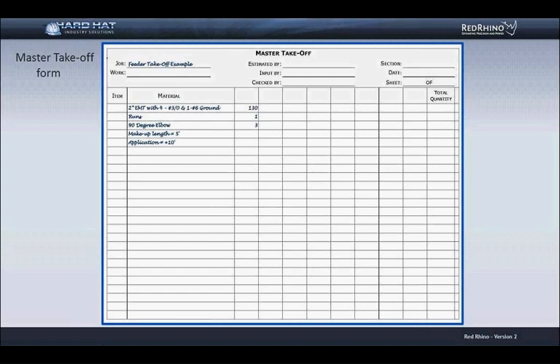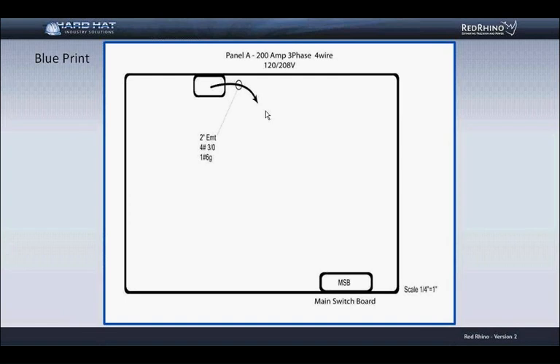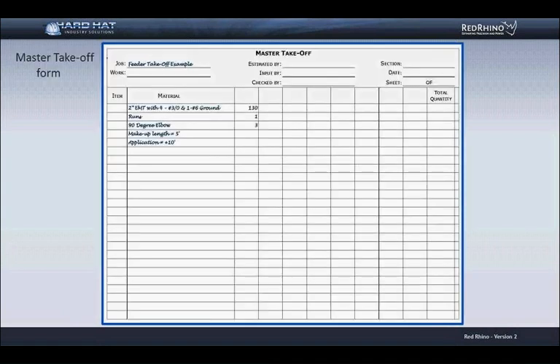I also have to count the 90-degree bends or elbows. By looking at the drawing, I know I need 1 90 going up out of one panel, 1 90 going out of the other panel, and 1 additional 90 for a total of 3 90-degree bends or elbows. Notice I did not take off couplings, connectors, or conduit supports. Red Rhino inputs those for you. I'll show you what I mean when I enter the materials into Red Rhino. On our takeoff sheet is an example how to write elbows. The example shows a quantity of 3. Later we will enter this into Red Rhino.